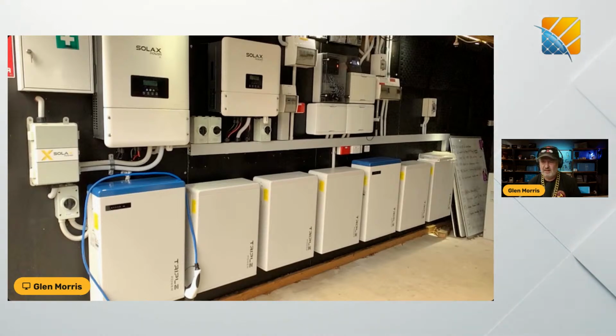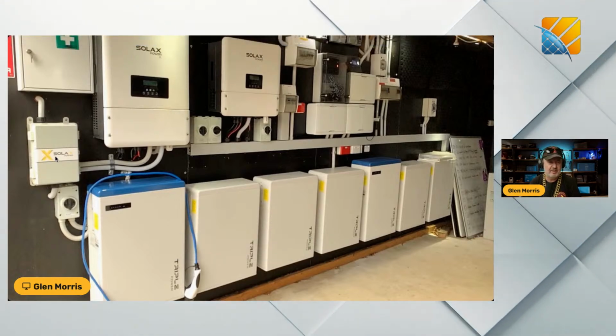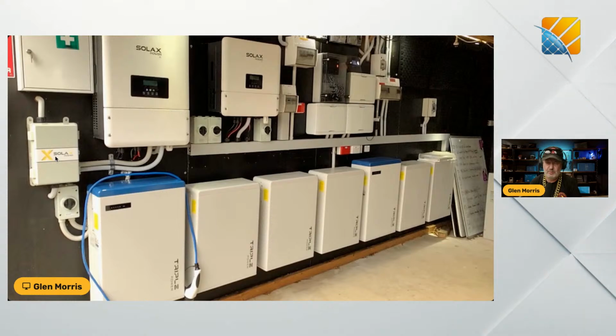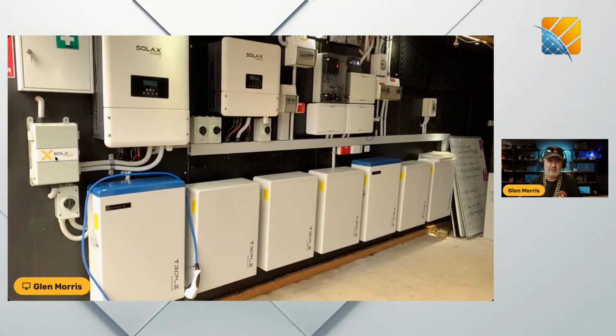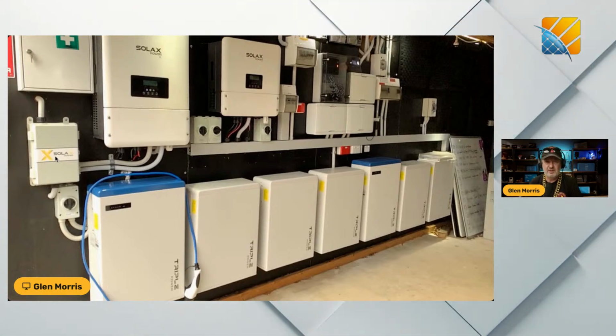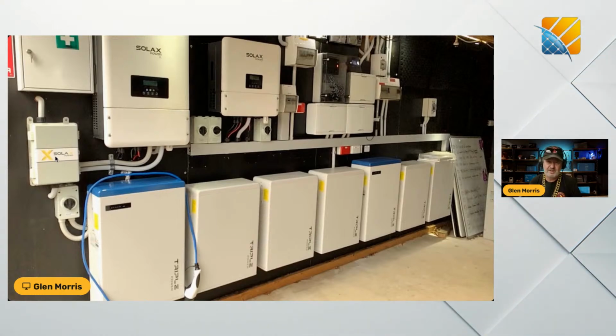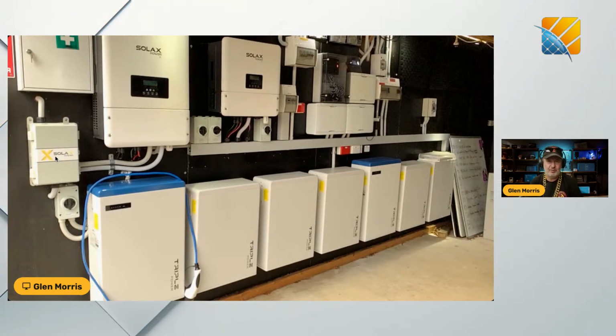So there you go. And on the left-hand side of the 10 kilowatt SolaX, there is a contactor inside that enclosure. It's an add-on product. That's so it can switch into backup mode using a contactor, so it will be able to run independently of the grid in 3-phase. This also has a feature which is not that common, which is called unbalanced load support. So when you've got solar and batteries connected and you're on grid, you don't have to produce the same amount of export on all 3 phases. So it can actually support one phase at a different rate to the other 2 phases.